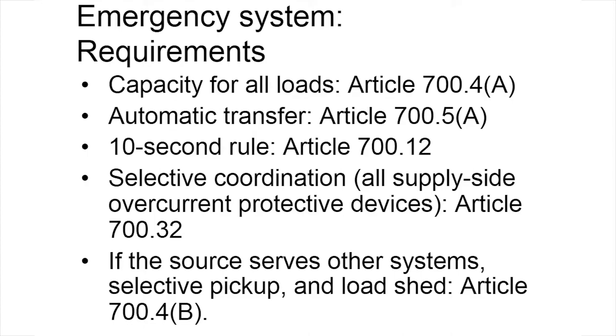Article 700.32 requires that emergency system overcurrent devices be selectively coordinated with all supply-side overcurrent protection devices. That means all the breakers and fuses in that system have to be coordinated. And by way of description of selective coordination, in a system that's selectively coordinated, only one overcurrent device will open to clear a fault, and that would be the upstream device that's closest to the fault. That'll restrict the outage to only those circuits that absolutely have to be de-energized.